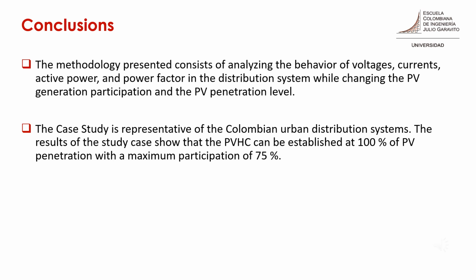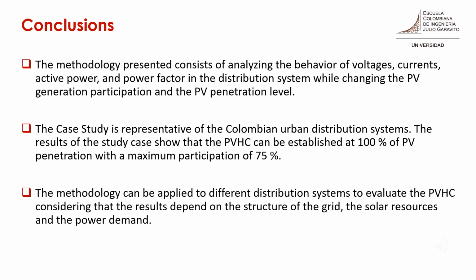The results of the study case show that the PV hosting capacity for this grid can be established at 100% of penetration with a maximum participation of 75%. The methodology can be applied to evaluate the PV hosting capacity, considering that the results depend on the structure of the grid, the solar resources, and the power demand.